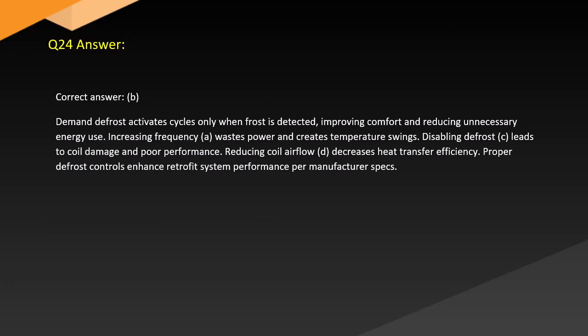Answer. Correct answer. B. Demand defrost activates cycles only when frost is detected, improving comfort and reducing unnecessary energy use. Increasing frequency, A, wastes power and creates temperature swings. Disabling defrost, C, leads to coil damage and poor performance, reducing coil airflow. D. Decreases heat transfer efficiency. Proper defrost controls enhance retrofit system performance per manufacturer specs.